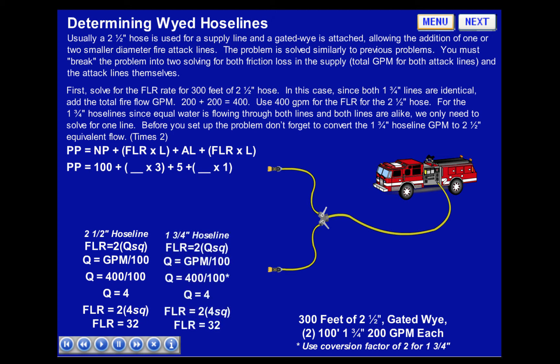For the 1¾-inch attack lines, FLR equals 2Q squared, Q equals GPM over 100. In this case, Q equals 400 divided by 100, because we take the original 200 GPM and multiply it by 2 — the conversion rate for 1¾-inch hose. So FLR equals 2 times 4 squared, which equals 32.